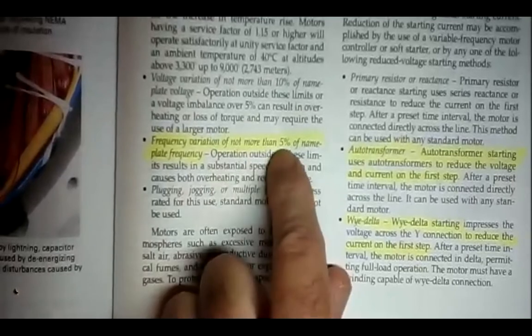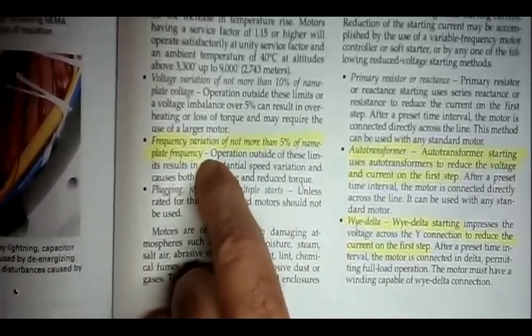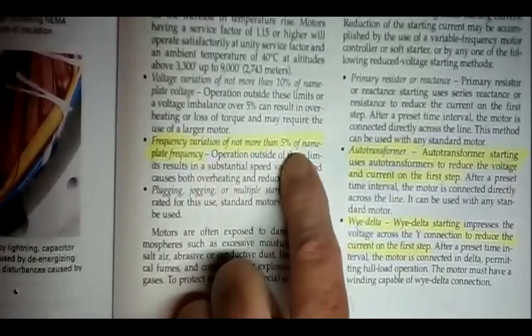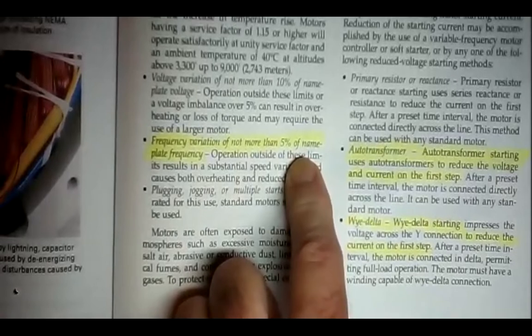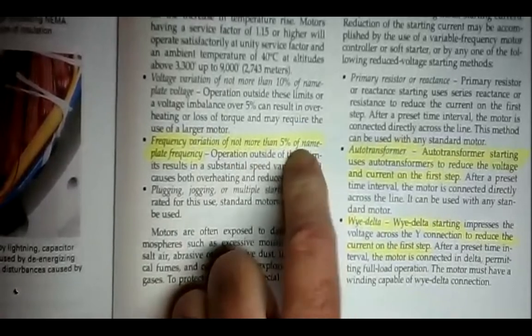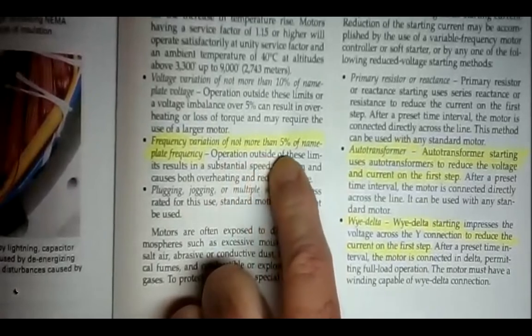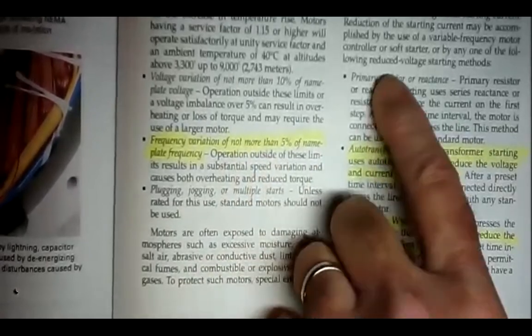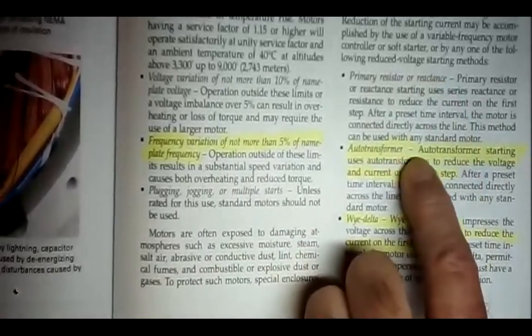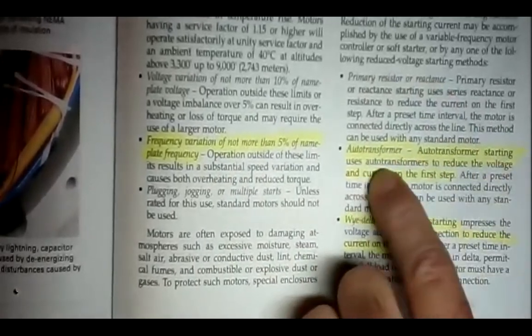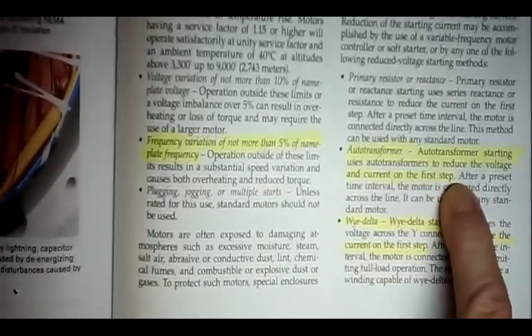frequency variations of not more than 5% of the nameplate frequency. So if it says 60 hertz, you shouldn't be less than 57 hertz. You shouldn't be more than 63 hertz, 5% of nameplate frequency. And then starting configurations. We have primary resistor or reactance starting. We have autotransformer starting. Autotransformer starting uses an autotransformer to reduce the voltage and current on the first step.